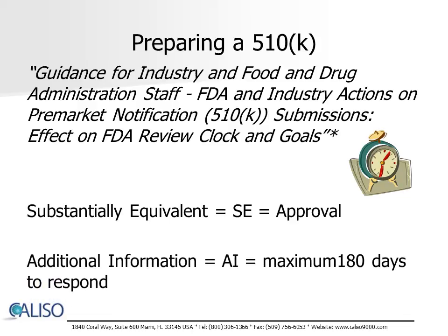If for some reason the submission is insufficient in any fashion, then the FDA will request additional information. A response to an FDA AI request is a submission of additional information addressing all of the deficiencies identified in the AI request. That allows the FDA to continue or complete the review and reach a decision on the 510(k) submission. The FDA will automatically grant a maximum of 180 days from the date of the AI request, even if the submitter has not requested an extension.